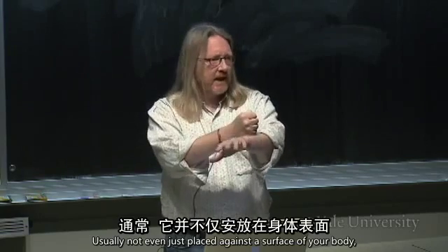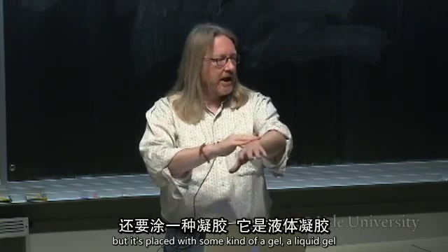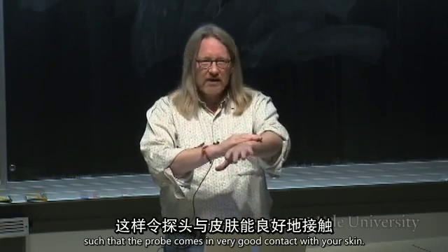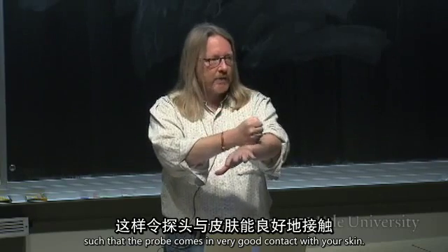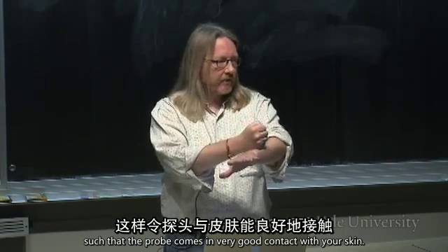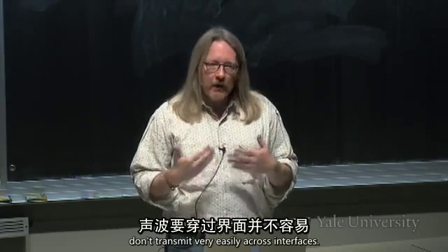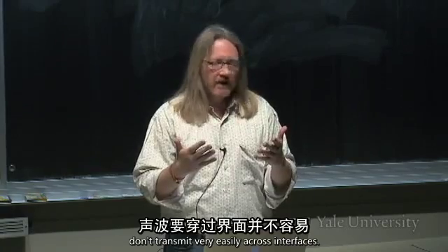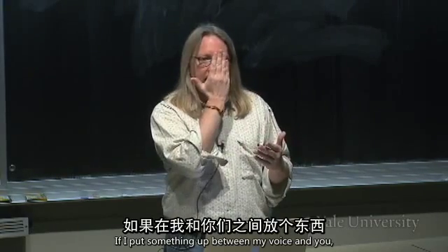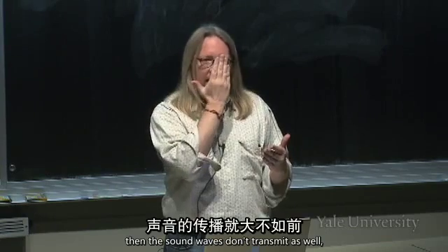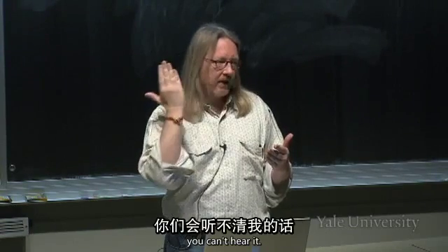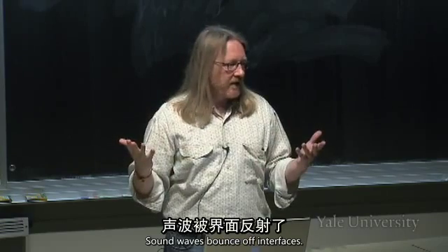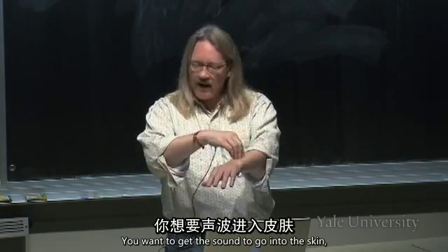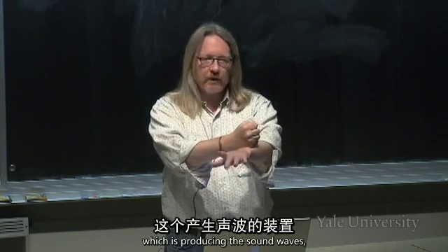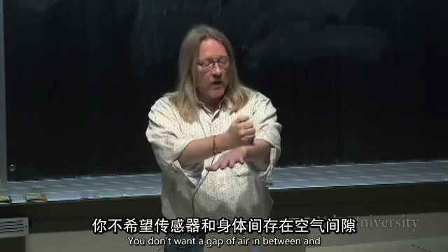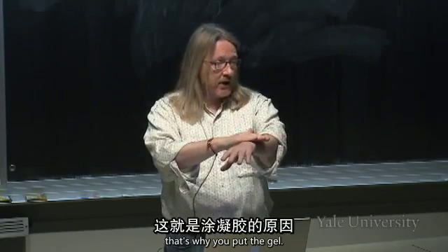And usually not even just placed against the surface of your body, but it's placed with some kind of a gel, a liquid gel, such that the probe comes in very good contact with your skin. And that's because sound waves don't transmit very easily across interfaces. Right? If I put something up between my voice and you, then the sound waves don't transmit as well. Right? You can't hear it. Sound waves bounce off interfaces. So you want to get the sound to go into the skin, you have to put the transducer, which is producing the sound waves, right up against the skin. And you don't want a gap of air in between, and that's why you put the gel.